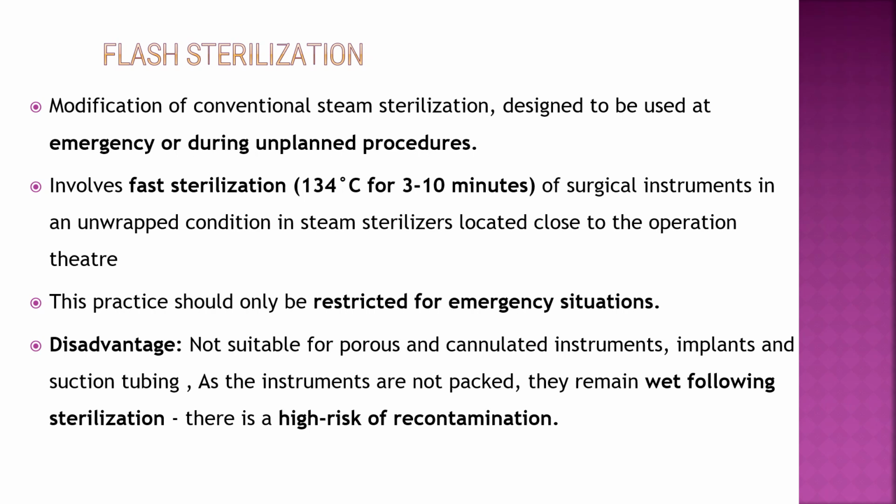Disadvantage: not suitable for porous or cannulated instruments or implants, because the instruments are not packed, so they remain wet following sterilization and there is a high risk of recontamination.